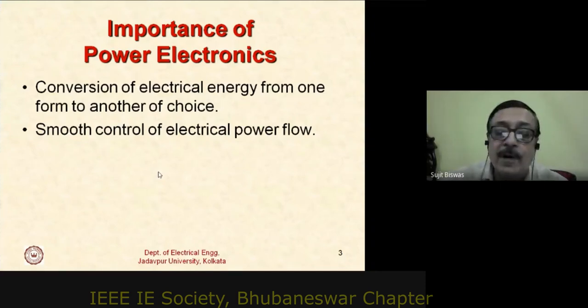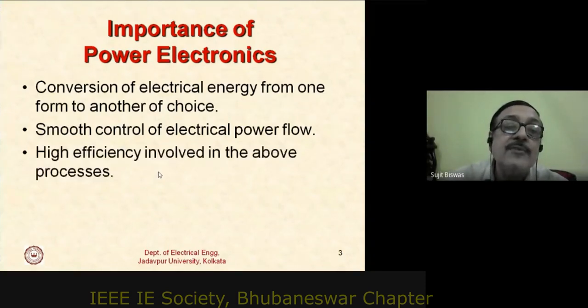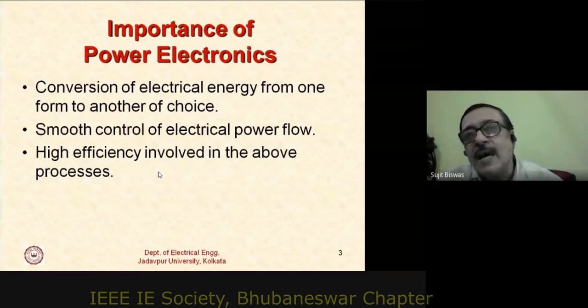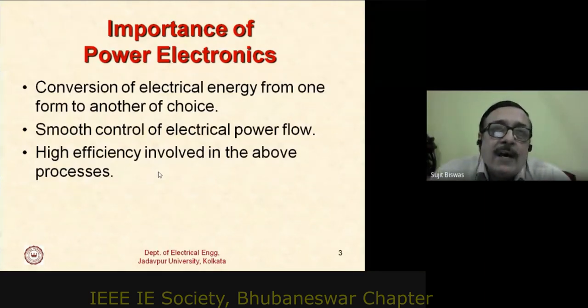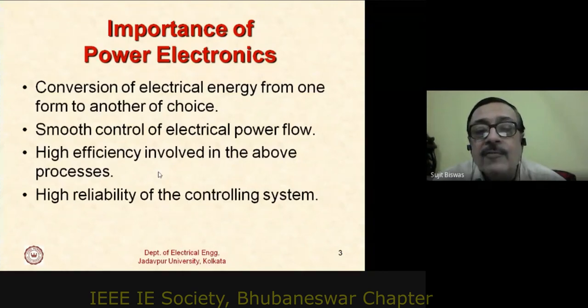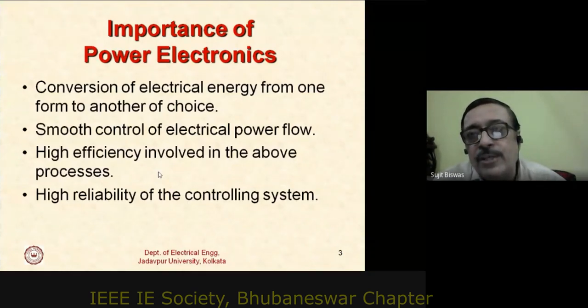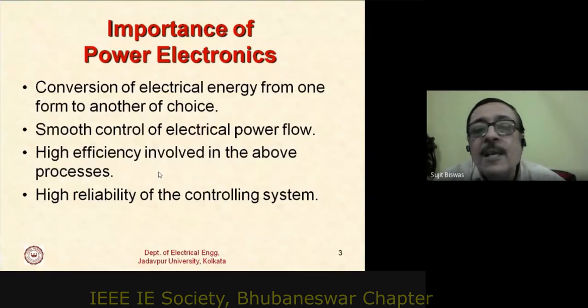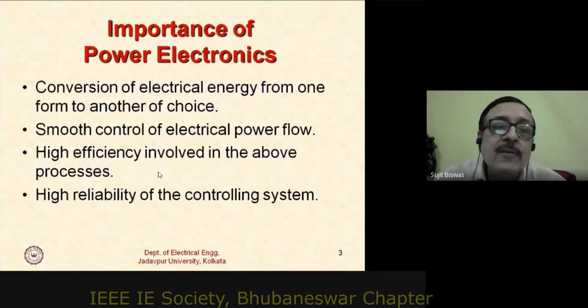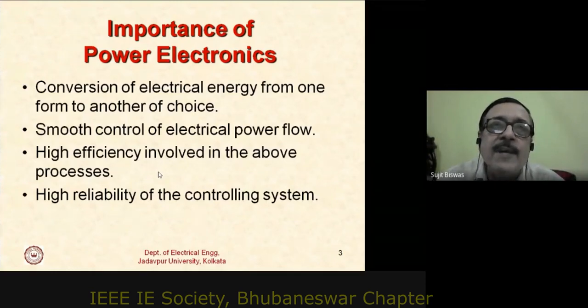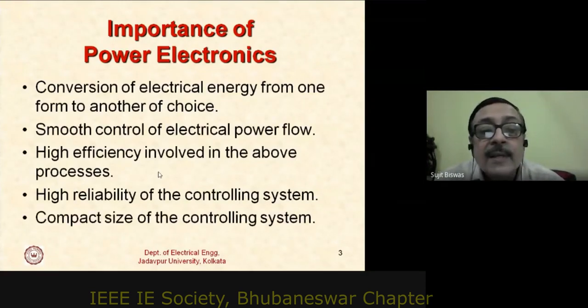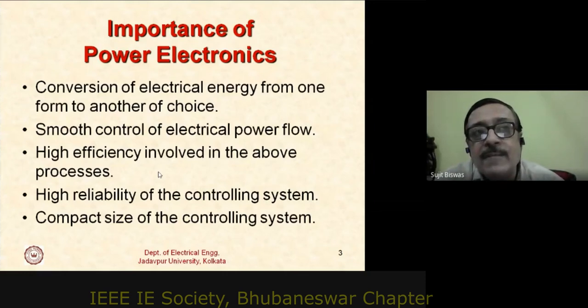Power electronics permits very smooth control of electrical power flow — no tap changing, no jumps, absolutely smooth. High efficiencies are involved; today we have inverters with efficiencies as high as 96 percent. Very high reliability is also expected: typical power electronic systems should have an MTBF of no less than 15 years, typically 20 years.